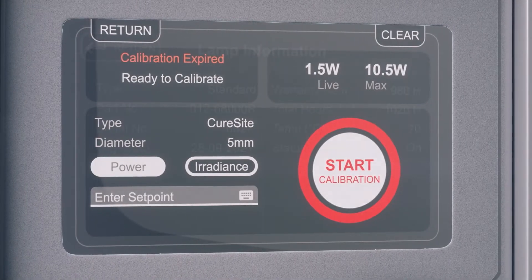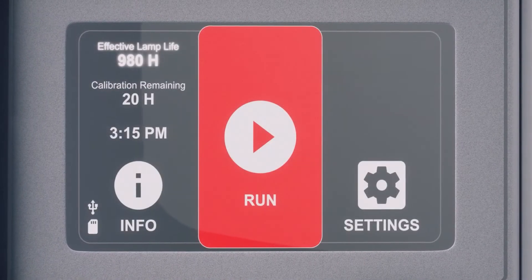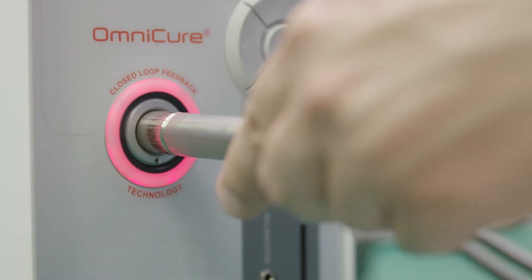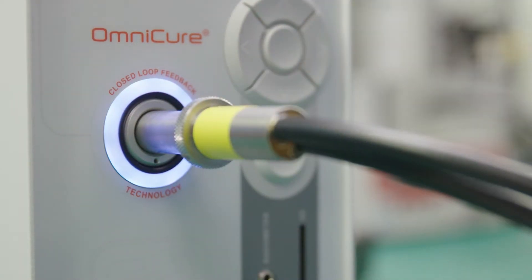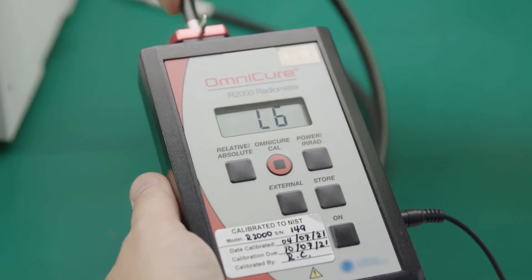The effective lamp life remaining is continually displayed based on the system's calibration state, lamp state, and output parameters, enabling you to schedule lamp replacements ahead of time at your convenience based on your specific process.